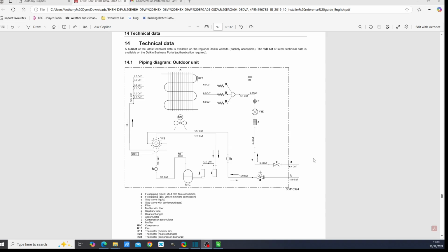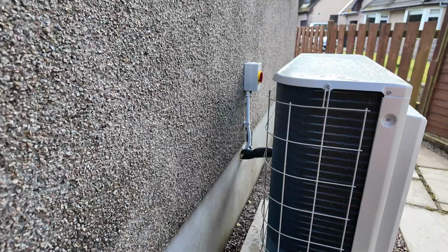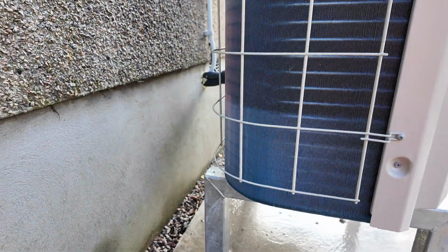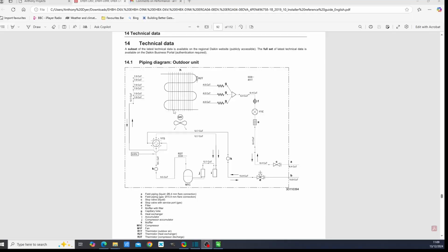And this is a problem because when you get to your evaporator coils, it splits. So what you'll find is that your liquids go down one capillary tube and your gases will hog your remaining capillary tubes. And that means that only a sixth or a third of your heat exchanger has actually got liquid running through it, absorbing latent heat from the air. And that's not an optimal situation. And the reason it's not an optimal situation is because this compressor is running all the time at the minimum. That's what's going on.